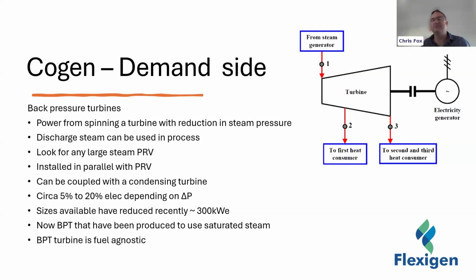In doing that, it's far more efficient than a power plant, because we're not only getting electricity, but also getting the heat from the steam. So in terms of finding an opportunity for a back pressure turbine, look for any large pressure reducing station or pressure reducing valve.